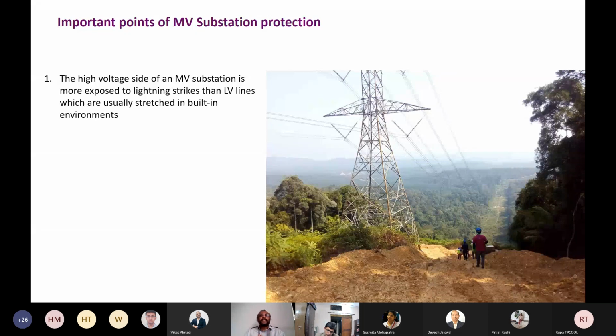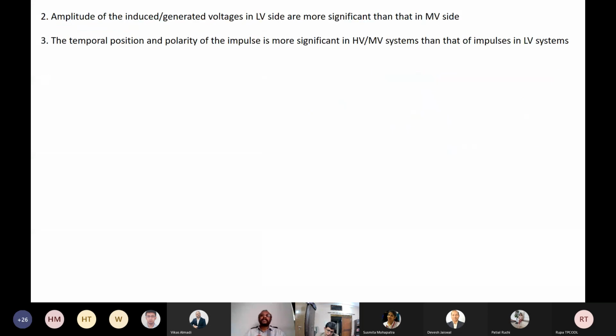Now, the amplitude of the induced or generated voltages on the LV side is more significant than on the MV side. Now, this is another important aspect. Although the number of surges that may come from the HV side is larger, the significance of the transients appearing at the substation from the LV side is more prominent. Why? The temporal position and polarity of the impulse is more significant in HV and MV systems than that of an impulse in LV systems.